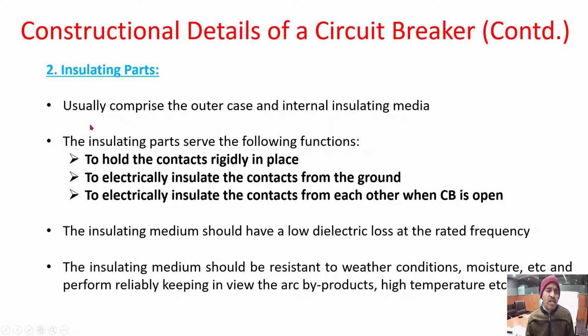Next are insulating parts. They usually comprise the outer case and the internal insulation media inside the circuit breaker. The internal insulation media as well as the outer case of the circuit breaker may consist of insulating parts. The insulating parts serve the following main functions. To hold the contacts rigidly in place. We have to keep the contacts in some physical place, so this is to hold the contacts rigidly in place, and to electrically insulate the contacts from the ground. This is also another function, and then to electrically insulate the contacts from each other when it is open.